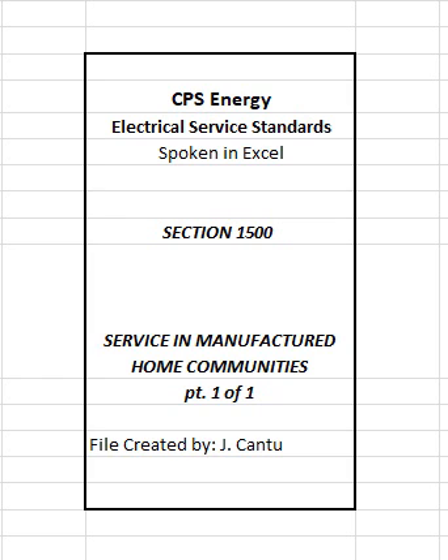4. Where customer elects not to use a meter pedestal, they may construct and utilize a metering equipment rack approved by CPS Energy for the mounting of single-position meter sockets and customers' service equipment. Refer to definition of metering equipment rack and Figure 1820. The CPS Energy customer service representative will review and approve proposed equipment installation design. Design submittal must include the number of meters, the size and rating of service equipment, conductor sizes, and estimated demand load requirements.